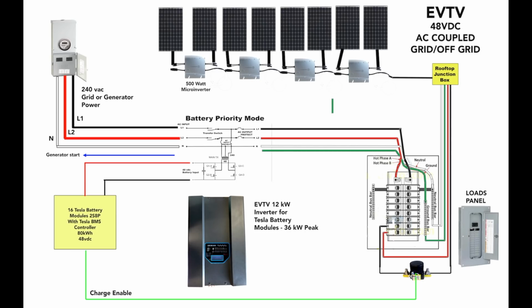We want to go through a contactor which is energized by our charge enable signal from the PowerPhase 100 battery module controller. And so we can turn on and off this array. Now, why would we want to turn it off? Well, if our battery gets full, we want to stop charging. We have to have some place for the excess power generated by this to go.